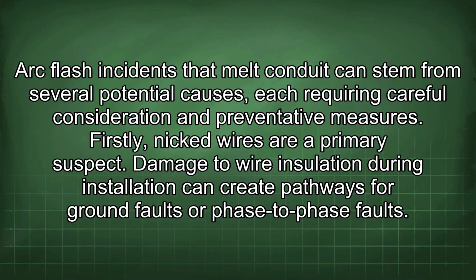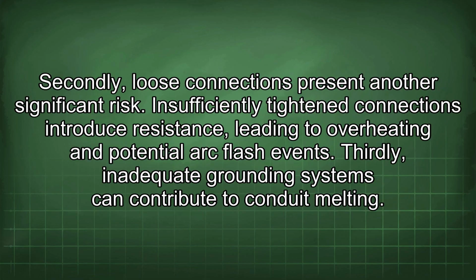Arc flash incidents that melt conduit can stem from several potential causes, each requiring careful consideration and preventative measures. Firstly, nicked wires are a primary suspect. Damage to wire insulation during installation can create pathways for ground faults or phase-to-phase faults. Secondly, loose connections present another significant risk. Insufficiently tightened connections introduce resistance, leading to overheating and potential arc flash events.